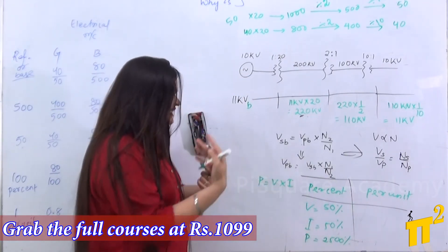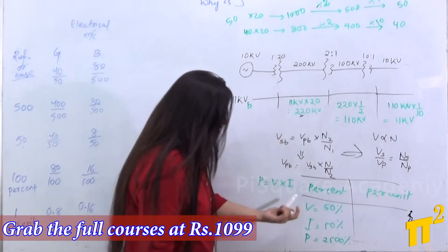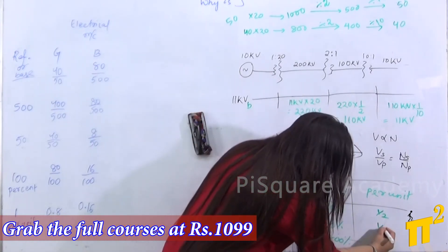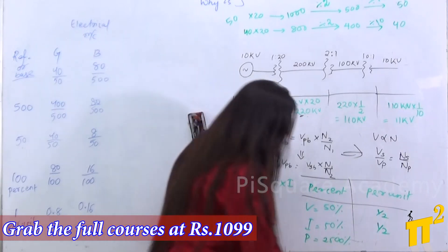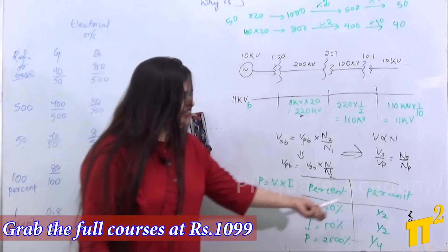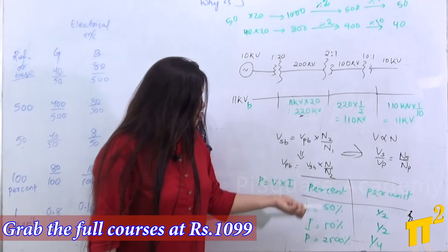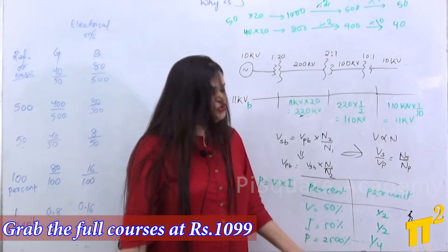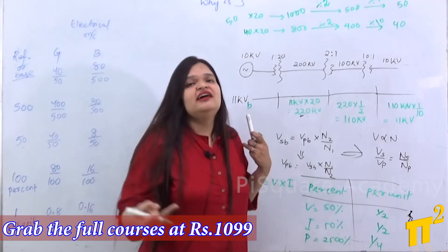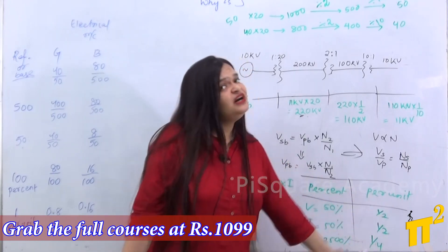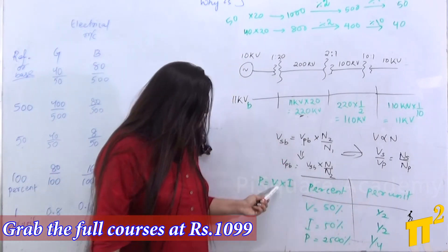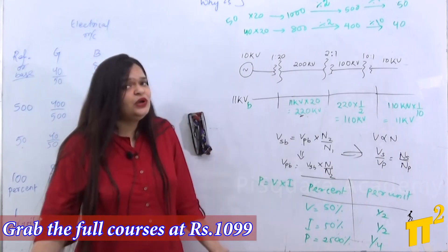But when I take it in per unit: voltage is reduced by half (0.5 pu), current is reduced by half (0.5 pu), and when I multiply both, power is reduced by one-fourth (0.25 pu). You can see the difference clearly. In percent, the product gives 2500 percent and you must divide by 100 again to get the result. In per unit, you simply multiply 1/2 × 1/2 = 1/4 — no extra division or multiplication needed.